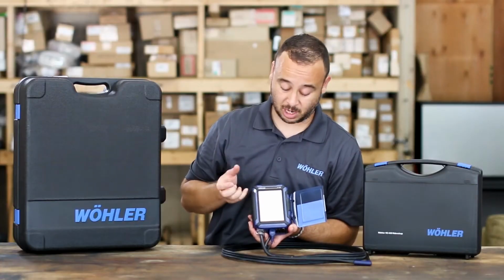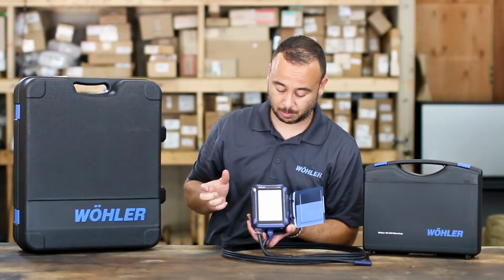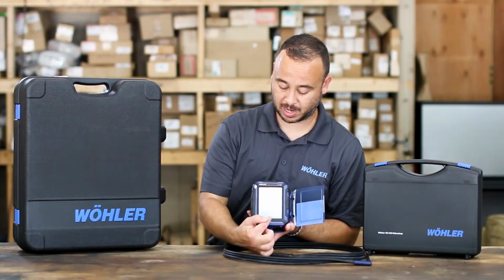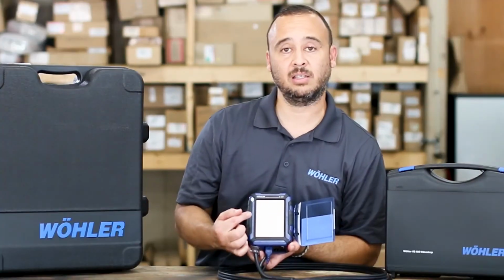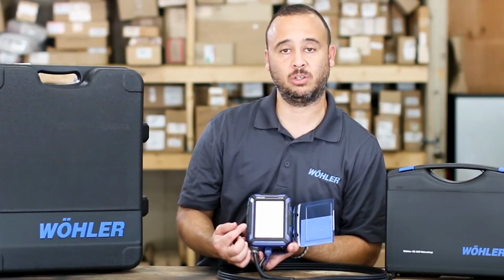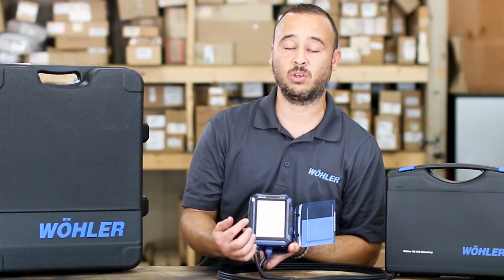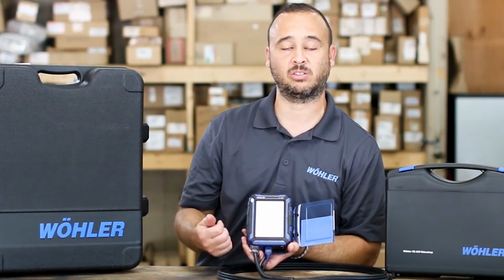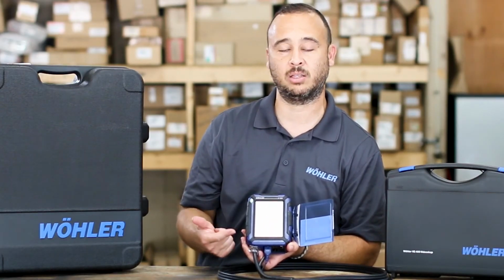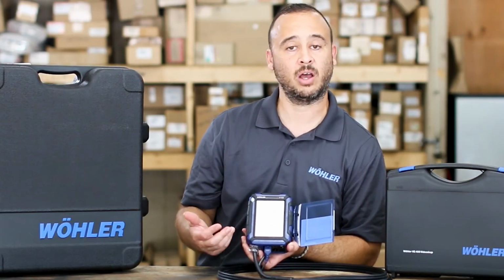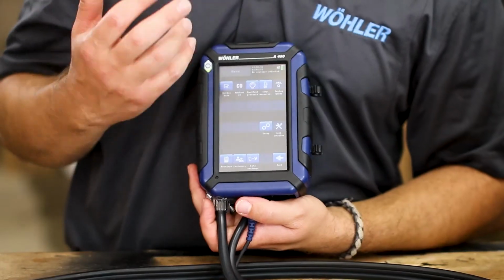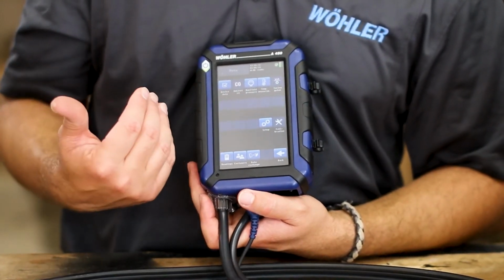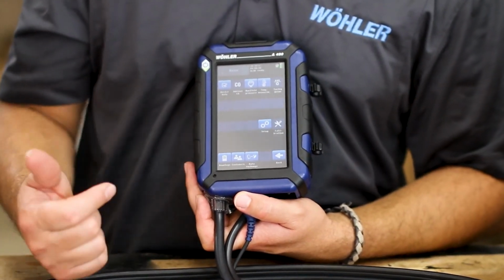You can go right into your combustion test by hitting the CO button and reading your graph completely from there. Besides the graph for combustion analysis, you can go back to the main screen to view and read all your other efficiency testing, such as stack temperature, ambient temperature, and other gases like oxygen. One key feature is that this unit has the ability to mirror a smartphone, Android or iPhone.